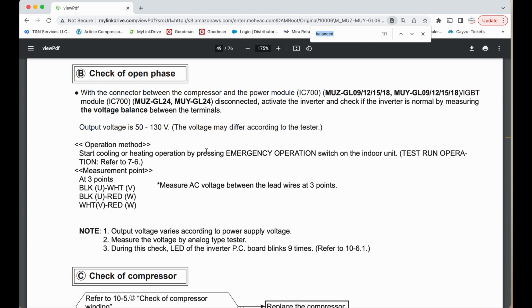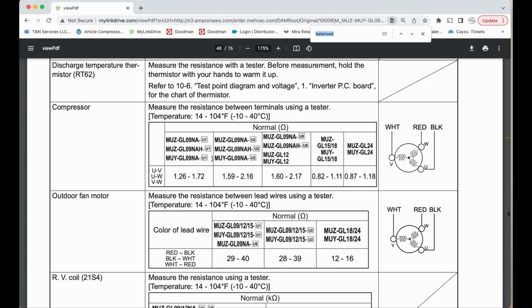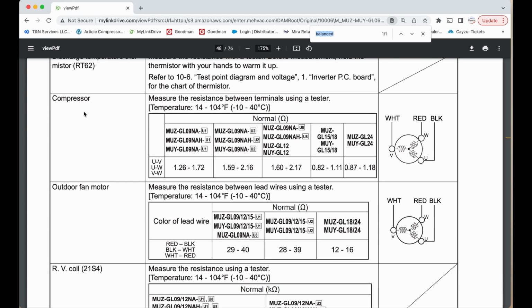Now if you wanted to ohm it out, you would just scroll up the page here, and here's the compressor, and it tells you what ohms you should be getting depending on the model number of the unit. So at 9,000, you should get 1.26 to 1.72, and that is a 9000-U1. Here's the reason the service reference number is so important. This is also a 9000, but it's a -U2, and the ohms rating is a little different. So that's why it's so important that you look at your service reference number to check it.